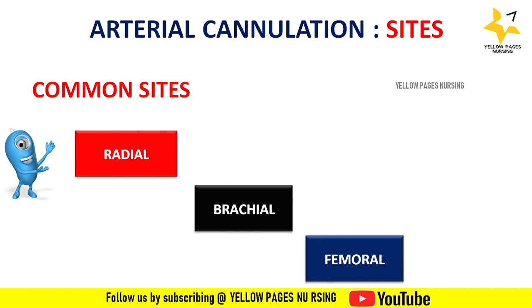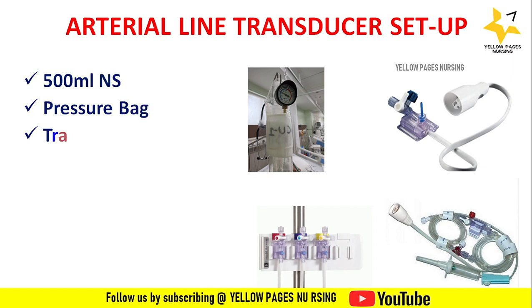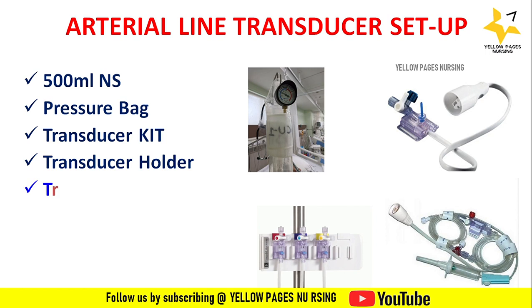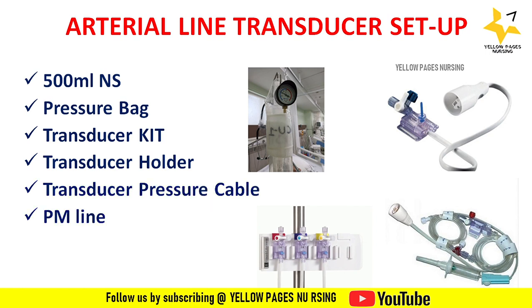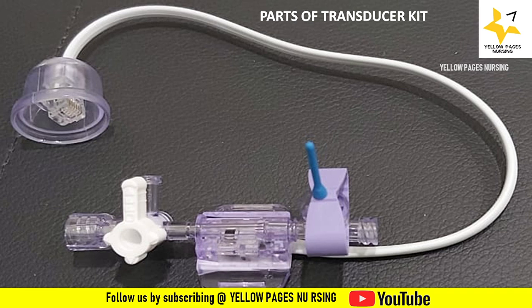For an arterial line transducer setup, we need a 500 ml normal saline pressure bag, transducer kit, transducer holder, transducer pressure cable, PM line, IV drip set, and syringe. The PM line and IV drip set may be pre-attached to the transducer set in some kits; if not, they need to be arranged separately.